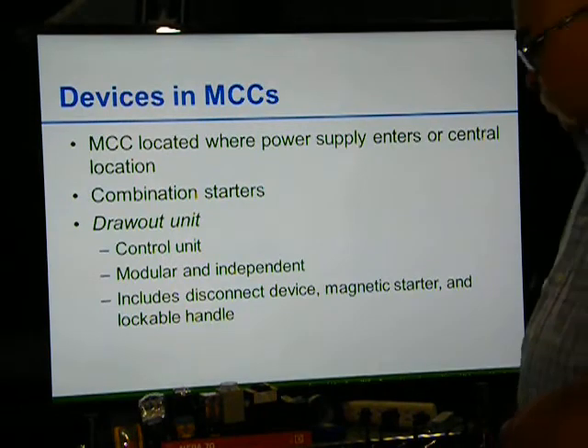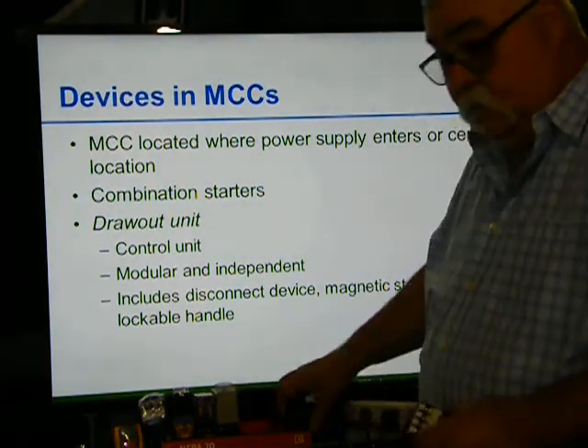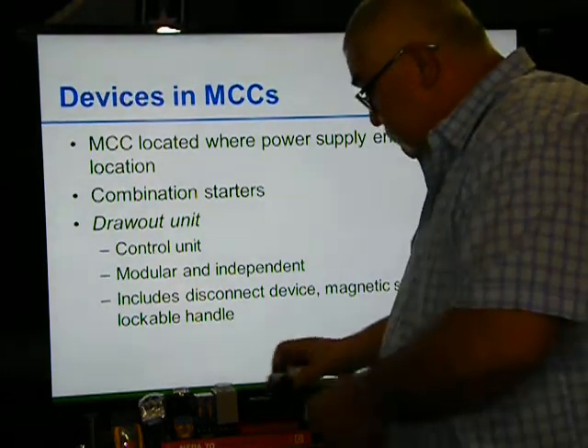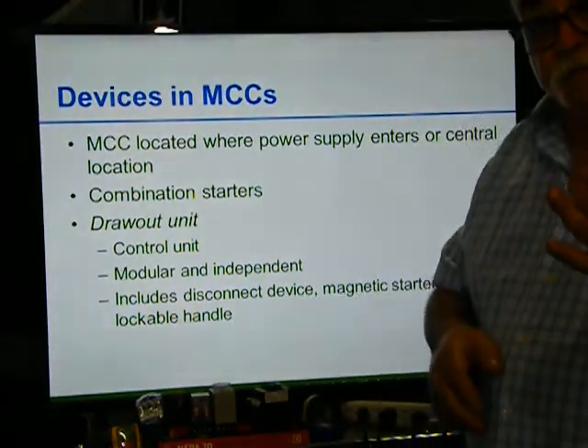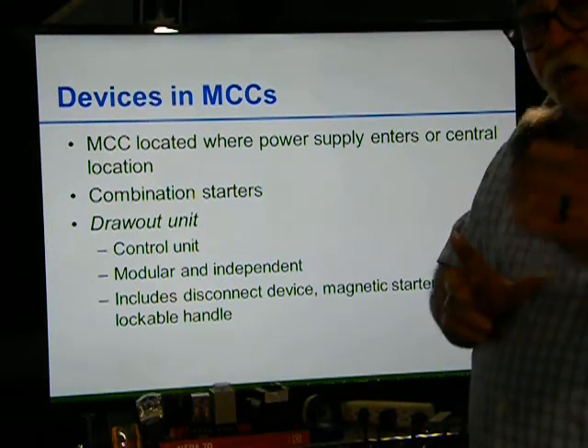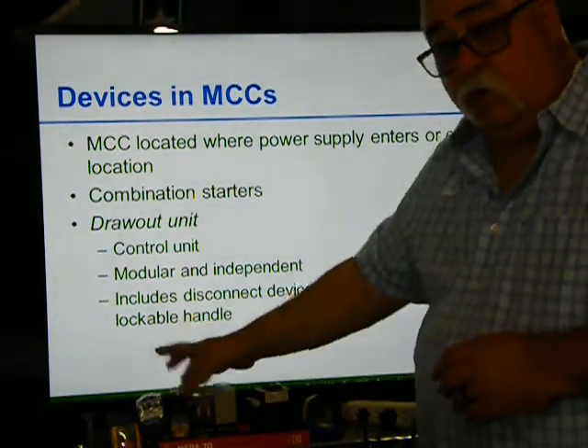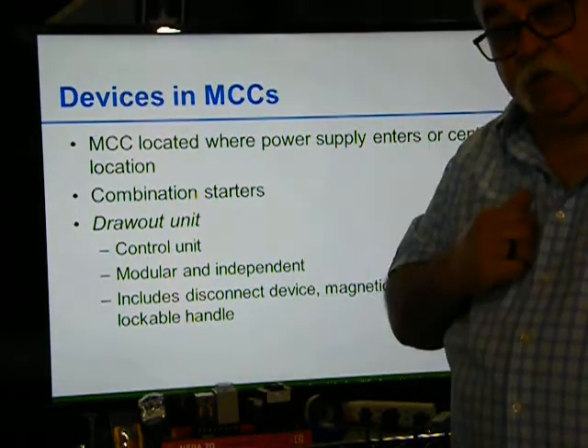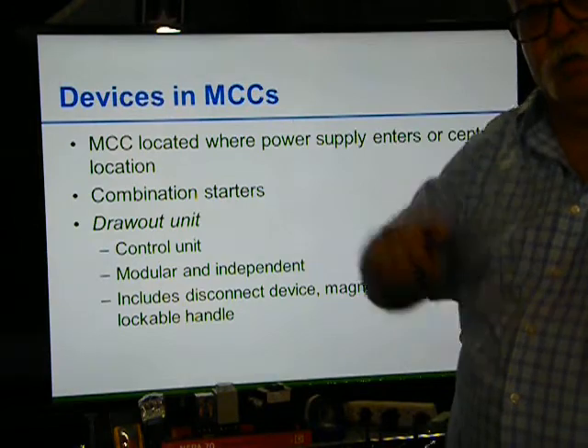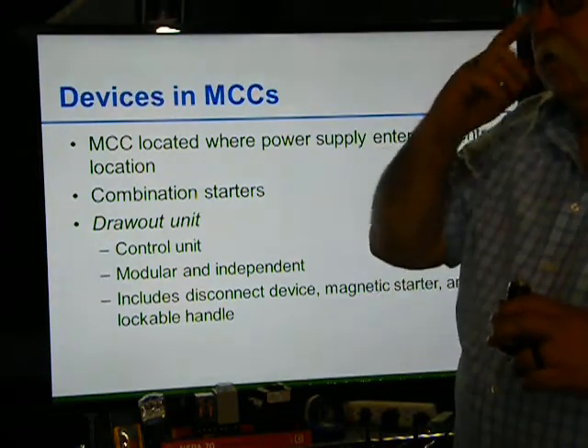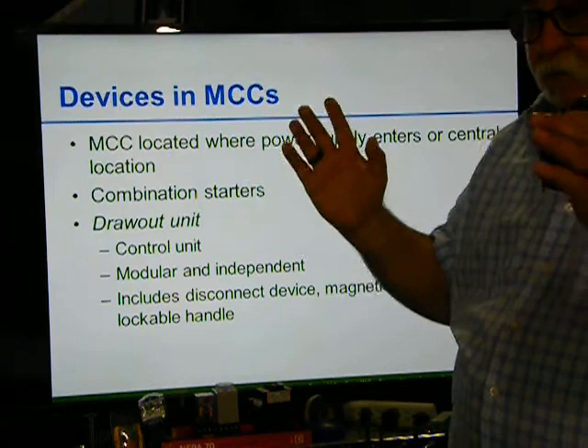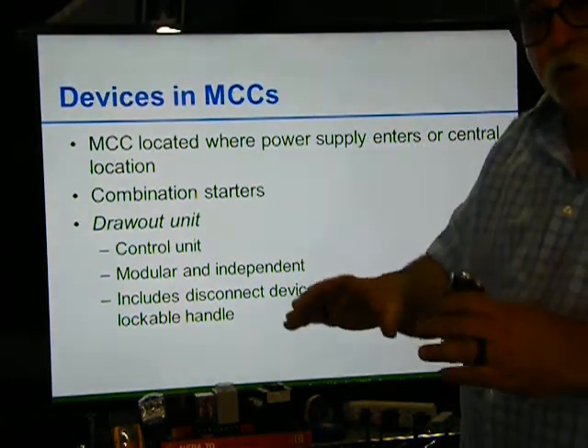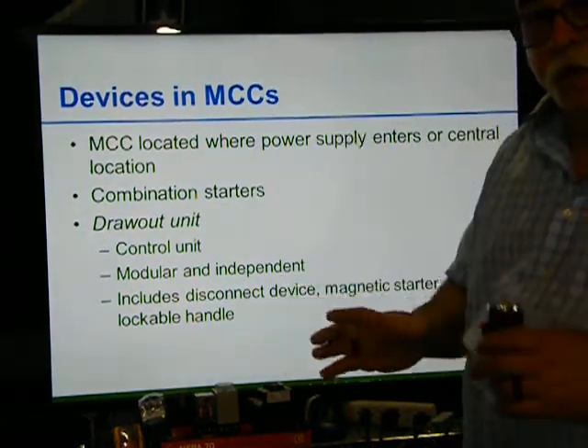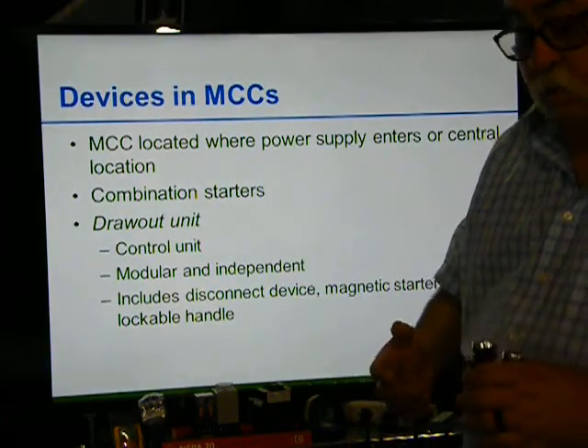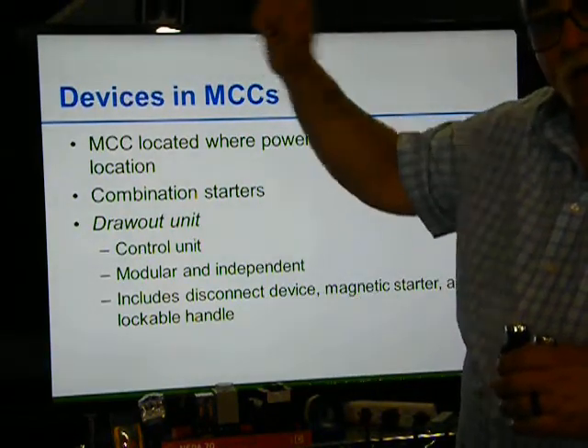So it has a combination starter, so it has the starter, the overloads, your stop starts. Sometimes they're not at the motor, they're on the door, where they might be remotely located, and that's what these allow you. You can have the stop starts on the MCC and have a remote somewhere else, like you got an exhaust fan, or you have a fume hood where somebody can go do work, and you have an exhaust out of that area because you're working on toxic fumes. So they could have a turn on, a turn off.